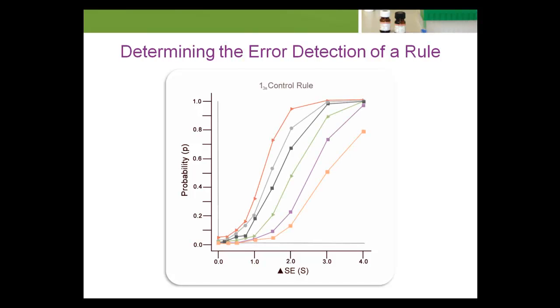The error detection characteristics of a QC rule can be plotted in what's called a power curve. The vertical axis is the probability of error detection. The horizontal axis is the size of the error. In general, as the size of the error grows, the probability of it being detected also grows. In this plot, we're examining the power curve of the 1-3-S rule when evaluated multiple times. The bottom curve is for a single evaluation. The top curve is for 20 evaluations. Notice that if the S-critical is above 4, the 1-3-S rule would likely be suitable.